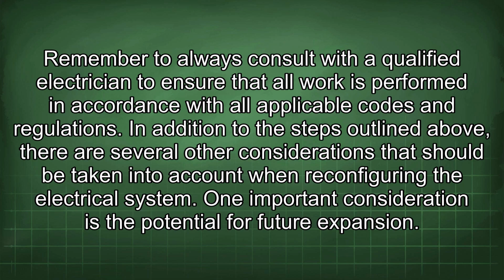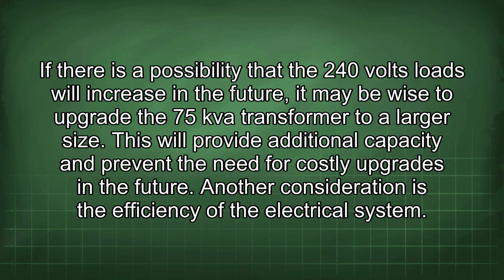In addition to the steps outlined above, there are several other considerations that should be taken into account when reconfiguring the electrical system. One important consideration is the potential for future expansion. If there is a possibility that the 240 volts loads will increase in the future, it may be wise to upgrade the 75 kVA transformer to a larger size. This will provide additional capacity and prevent the need for costly upgrades in the future.